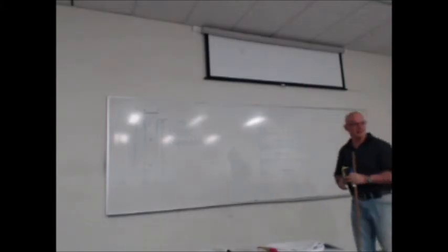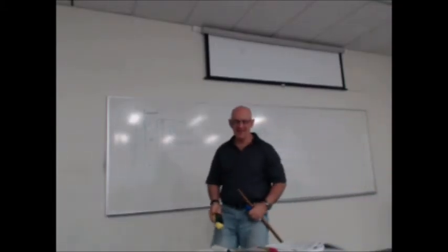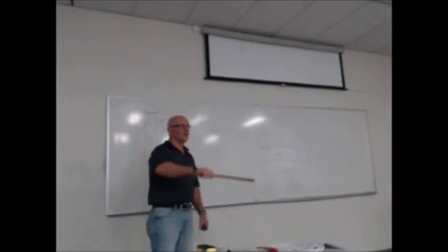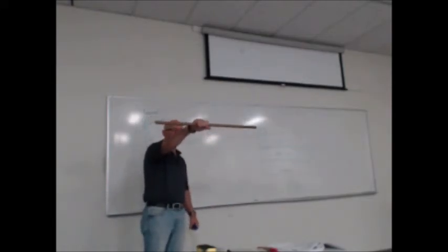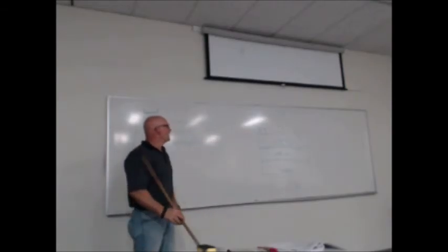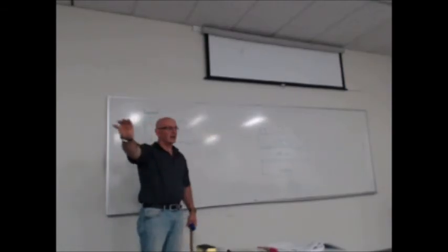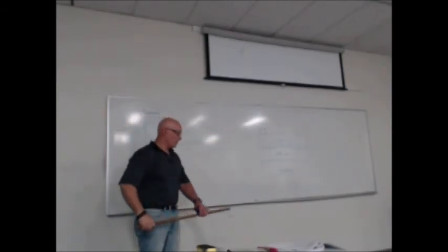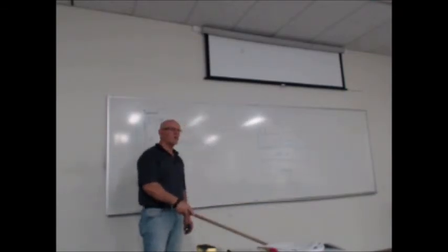Oh, sorry. Yeah, you're right. Upstairs. I'm thinking of the thermostat. The thermostat's got to be in the middle of that wall, at about two-thirds height. Thermostat's 1500. That's the optimum height. That's the air you're reading at that height. But yeah, you put your return air down the bottom, not in a cupboard.